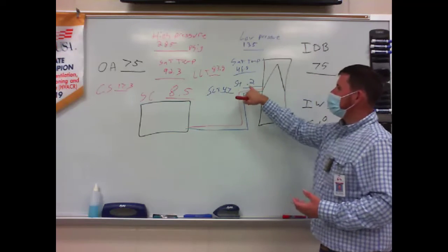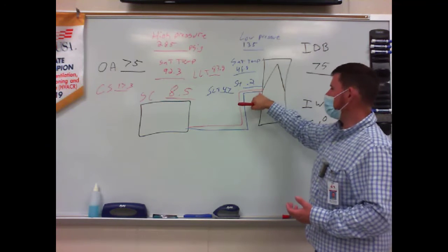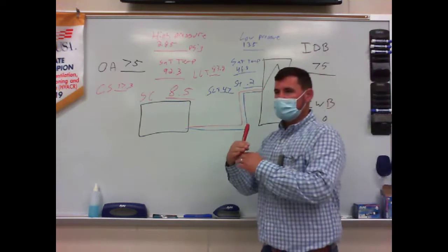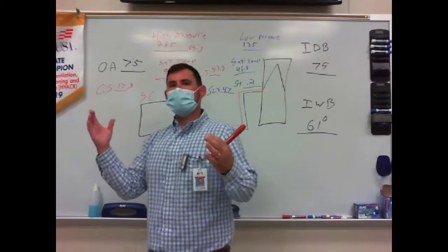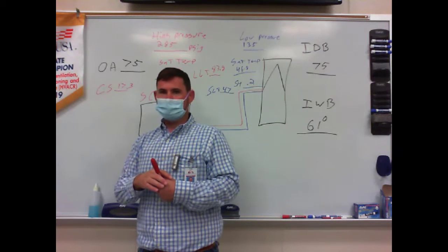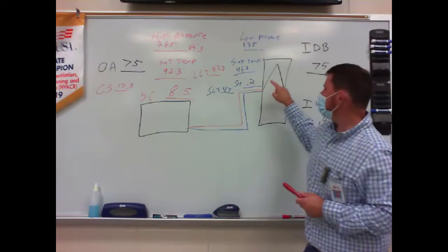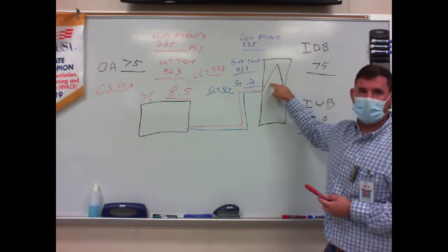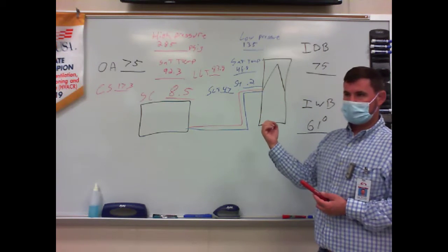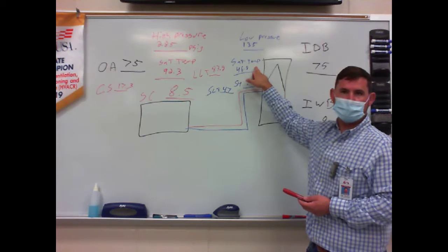What's actually happened, if that sensing bulb on that TXV senses that line temperature correctly and is insulated, if it sees that low of a superheat, should it open up to let more refrigerant in, or should it close to restrict the amount of refrigerant? It should close, right? As it closes, we'll get less refrigerant in that coil. So my superheat should start going up, correct? But what's going to happen to my pressure in there too if there's less refrigerant?